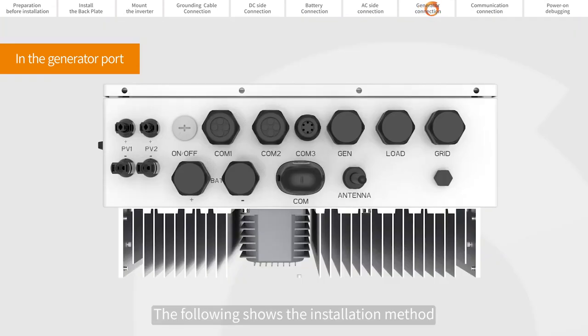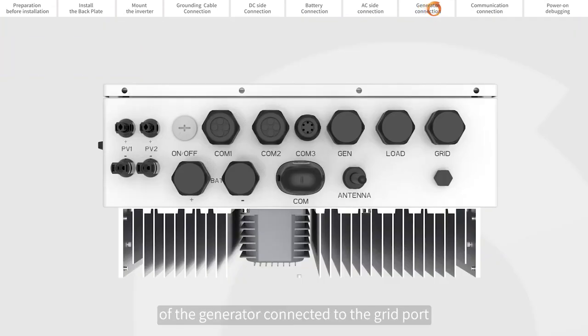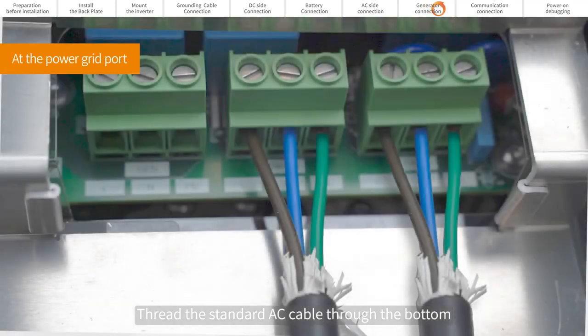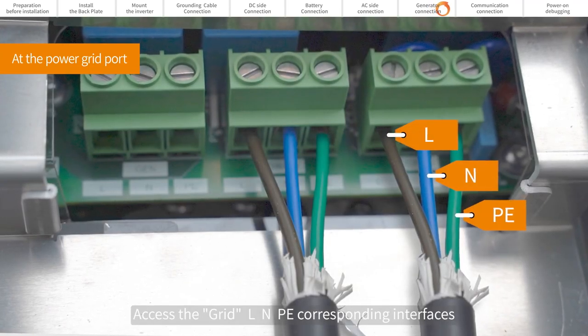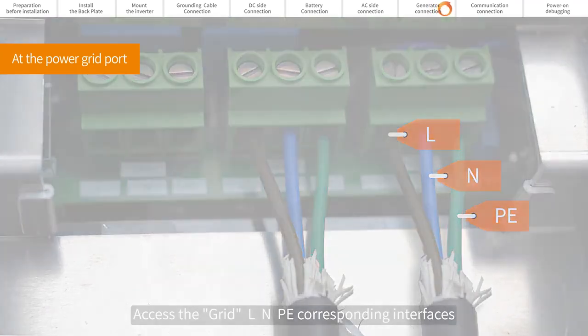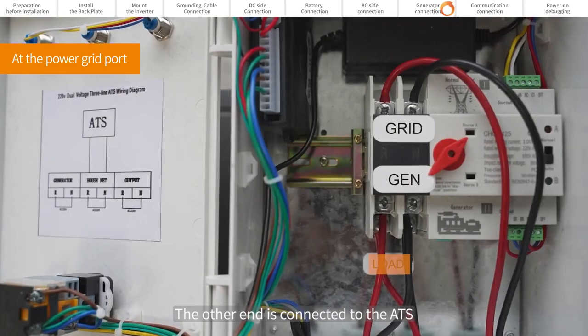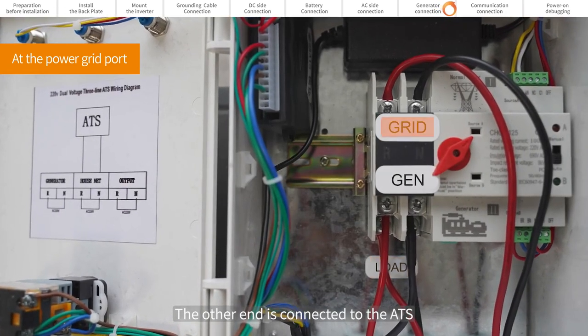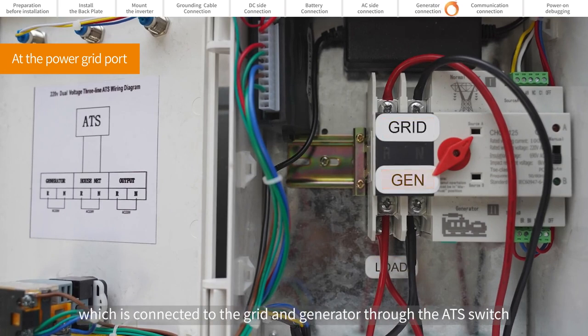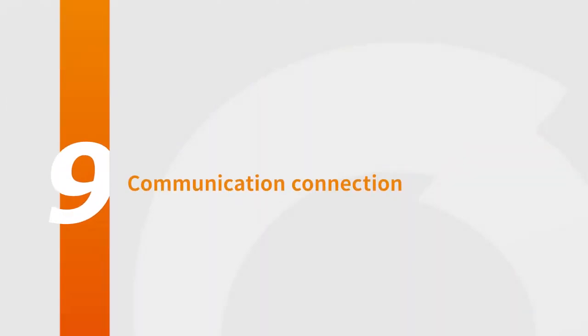The following shows the installation method of the generator connected to the grid port. Thread the standard AC cable through the bottom of the inverter grid port. Access the grid L, N, PE corresponding interfaces. The other end is connected to the automatic transfer switch, which is connected to the grid and generator respectively. Communication connection.